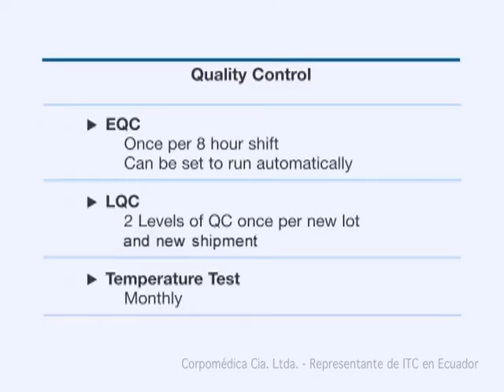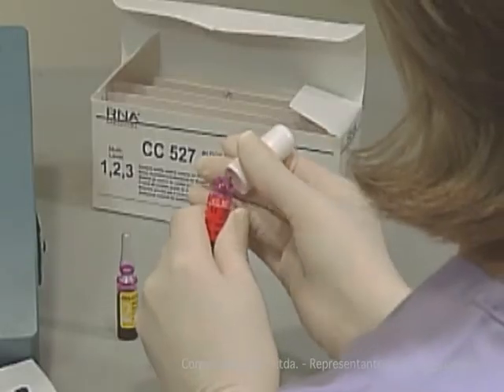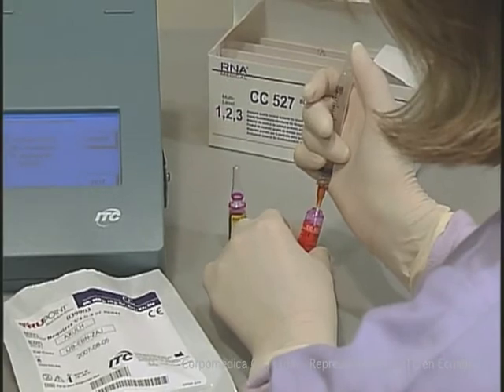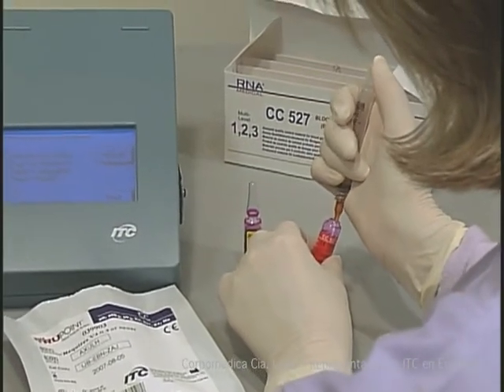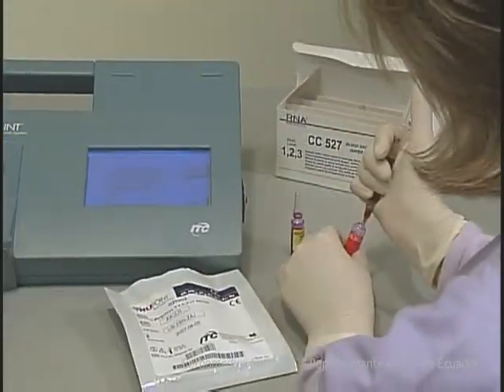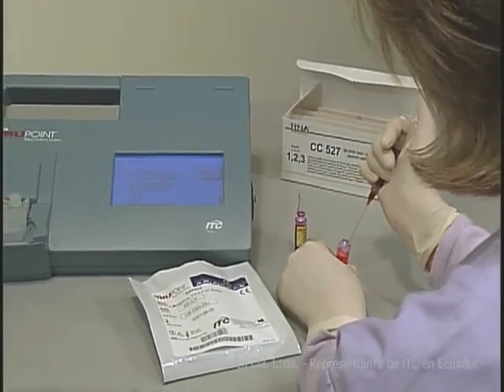After implementing your analyzer, ITC recommends that you include the following in your quality control program: electronic quality control performed every 8-hour shift, 2 levels of liquid quality control for each new lot and shipment of cartridges, and a temperature test performed monthly. Technique in handling liquid quality controls is very important. To perform quality control testing, use RNA controls for all cartridges except the creatinine cartridge.